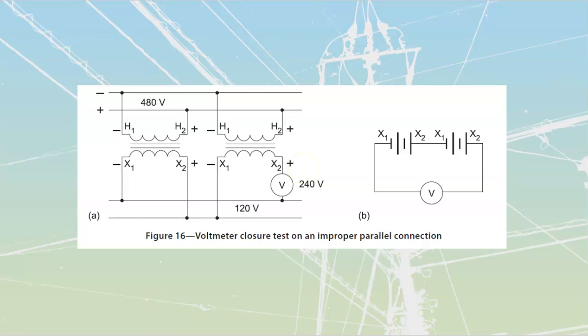The second case is the same setup: we've got a transformer we're paralleling in, but we don't know whether we've got that connection done correctly. We've connected on our high side — here's my existing, here's my new one. I connect my H1s on my high side, and my H2 to the opposite line so the H2s are matched. Then I take one of my lines and connect it onto something — we don't know which line it is yet, so it's connected to one of these lines over here.